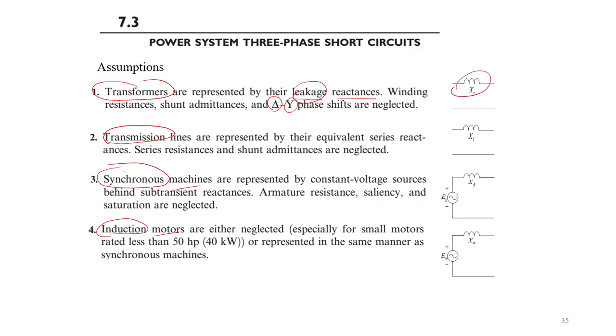Assumption number two concerns transmission lines. Lines are represented by their equivalent series reactance. The series resistances and shunt admittances are neglected. Especially for power transmission, the resistive part of the transmission line is normally much less than the reactive part, so it is omitted.